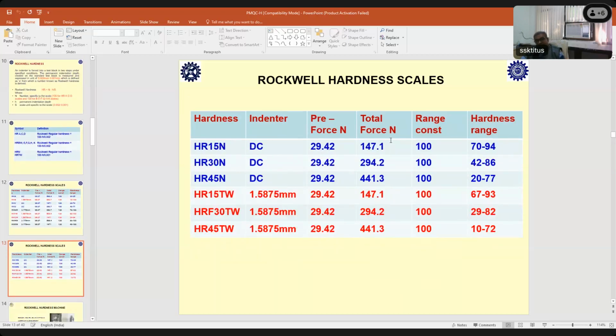It also has superficial scales. In the regular scales you are applying 10 kg force, but there are some materials you will not be able to penetrate much, so you have to use the superficial scale. In the case of superficial scales, you can use the diamond indenter, and also the ball indenter of 1.5875 mm diameter. Here the difference is that for the preliminary force you are applying 3 kg, and for the total force, HR 15 means 15 kg with the preliminary force of 3 kg. HR 30 is the 3 kg preliminary force and a total force of 30 kg.